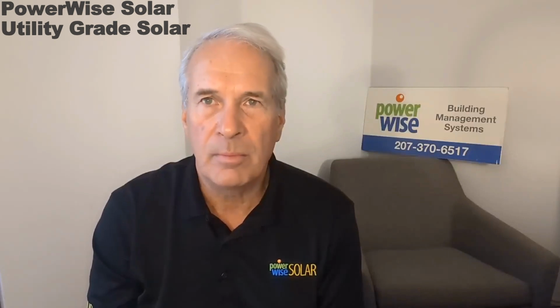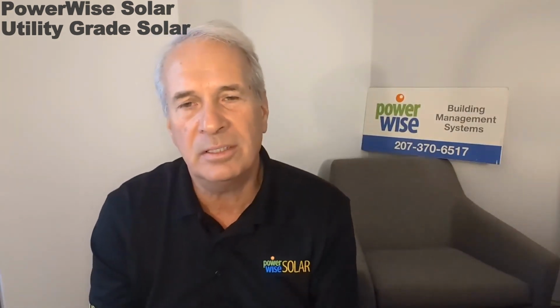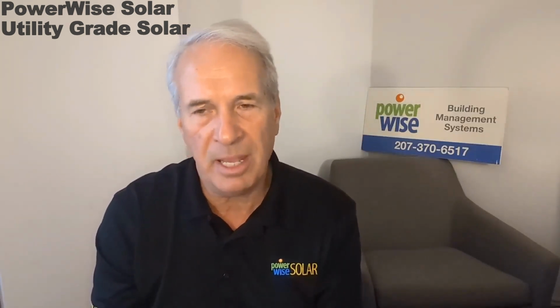Okay. And in terms of powering these met stations, are they normally self-powered? Are they powered off the solar panels themselves? How is that configured? Most of the time, we get them connected with 120 volts AC power to the station, but they all pretty much need to have some kind of backup power. So we include a charge controller on the battery, so the line voltage keeps the batteries topped up, and if there's a power loss, the battery kicks in. We normally size the battery for 48 to 72 hours of operation.